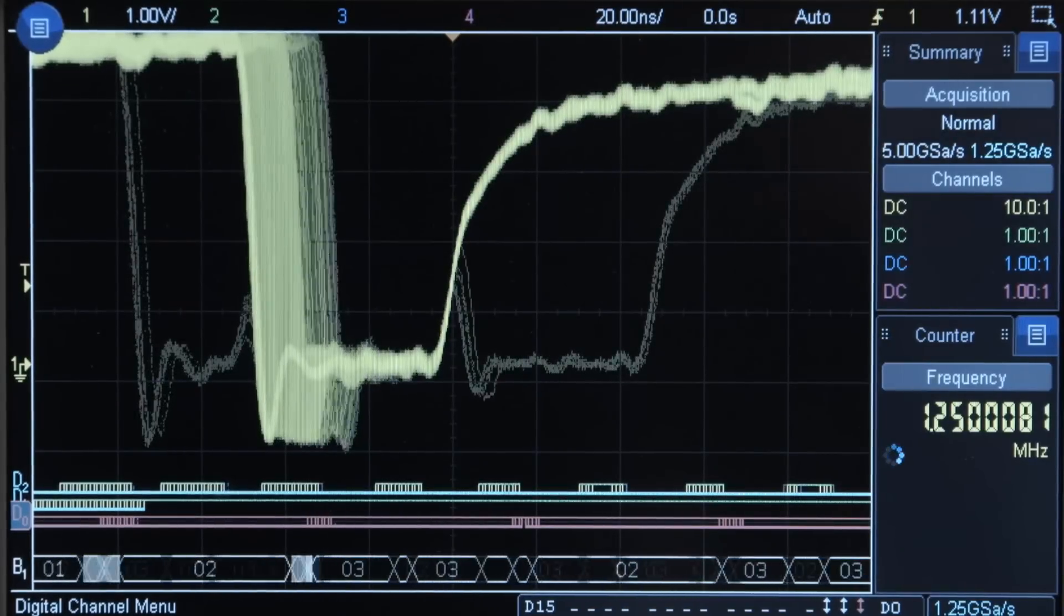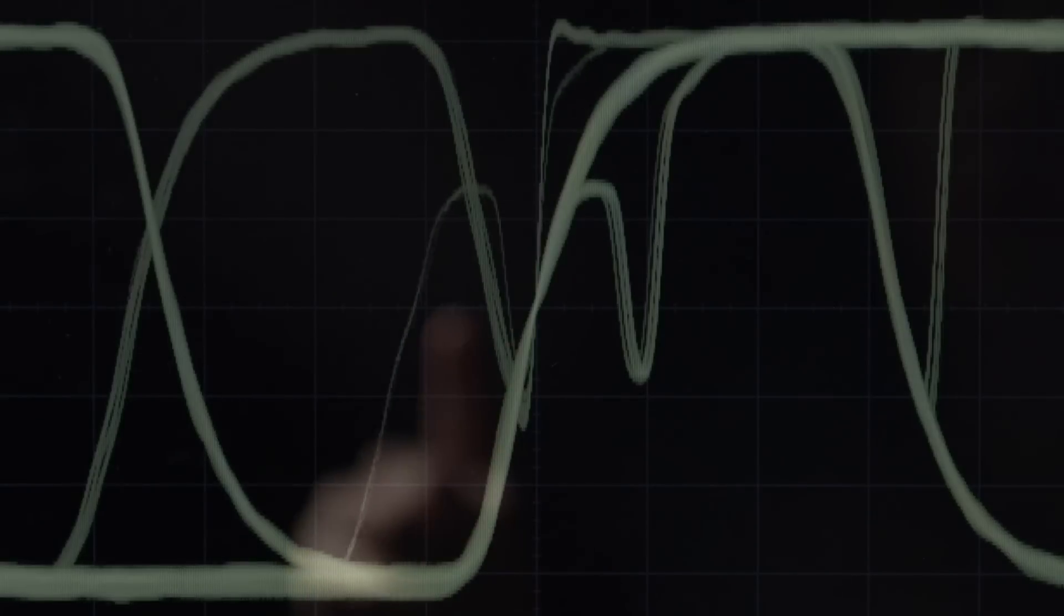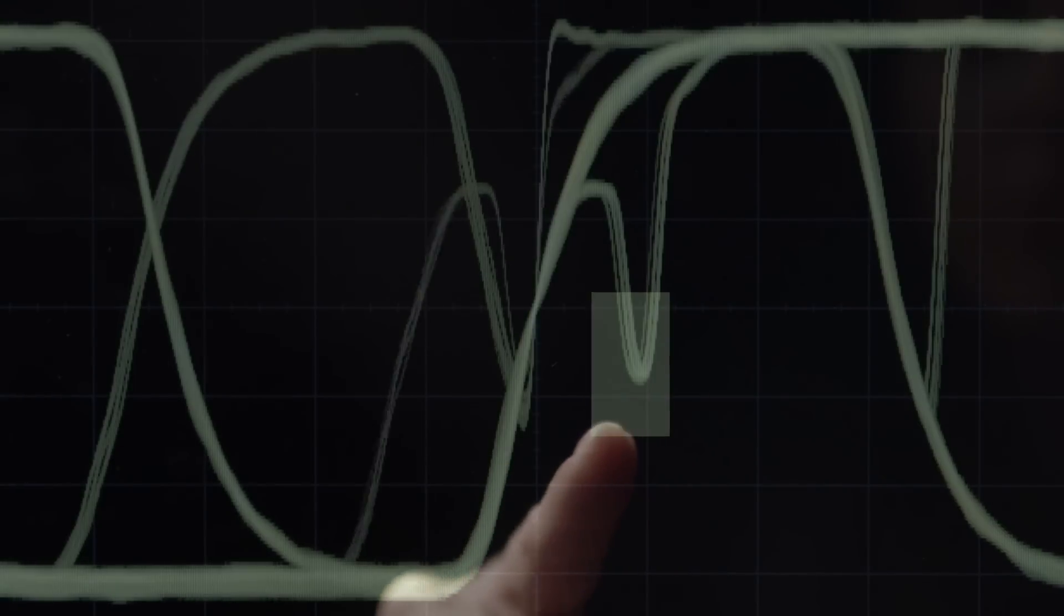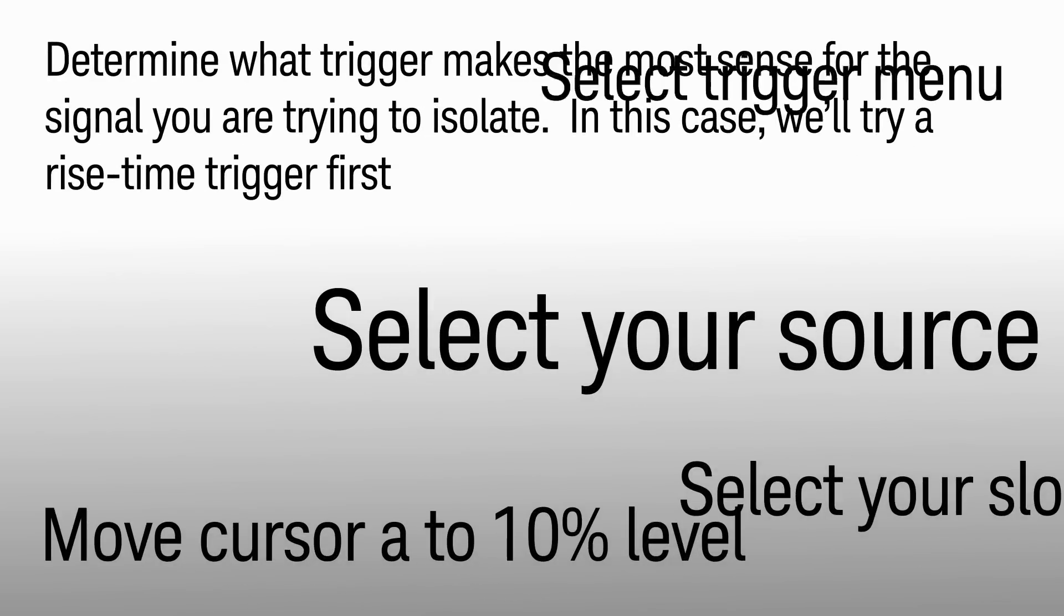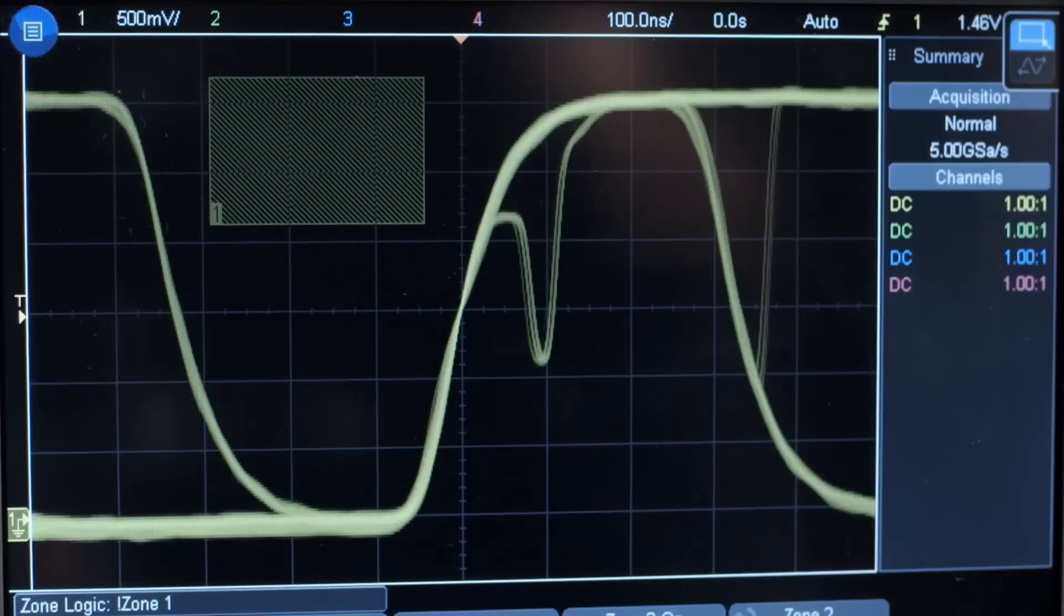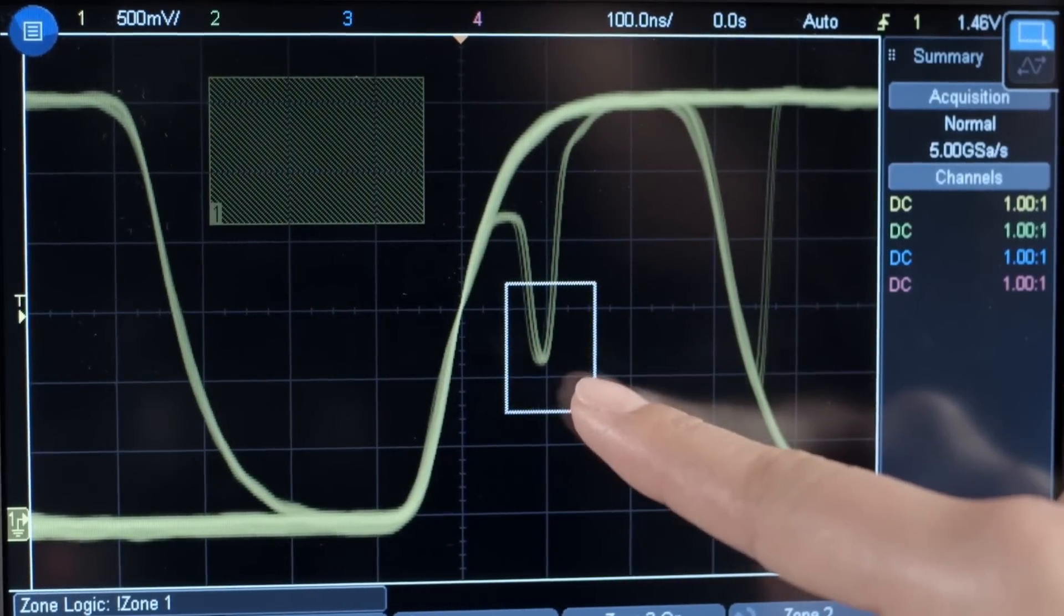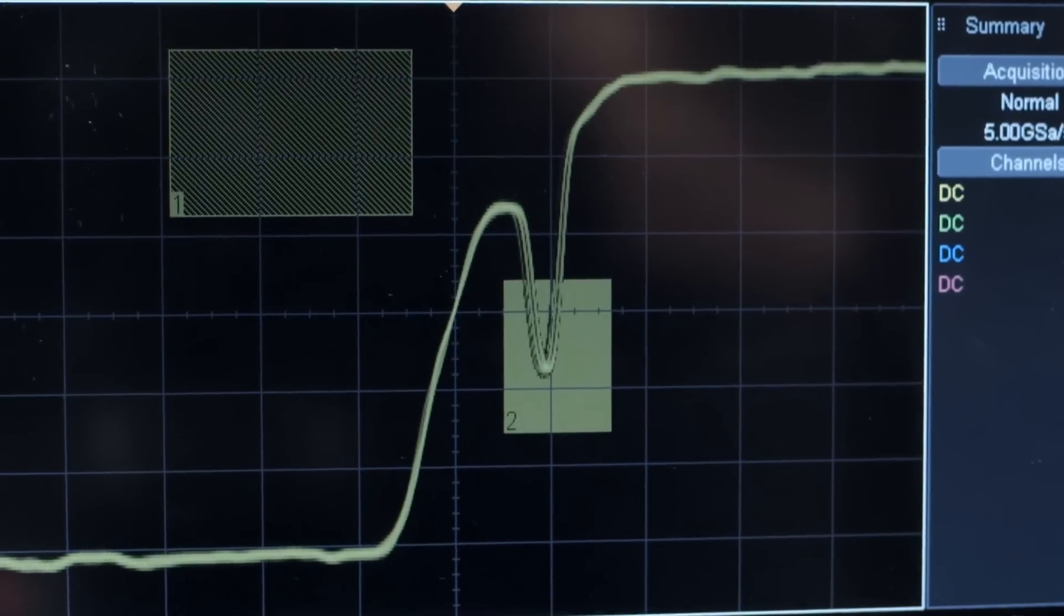Once you've identified an anomaly, isolate it with zone trigger. On a traditional scope, triggering can involve a dozen or more steps and many test engineers simply give up. No more. Now simply draw a box around the signal area of interest, select with the tap of your finger, and the problem is isolated in seconds.